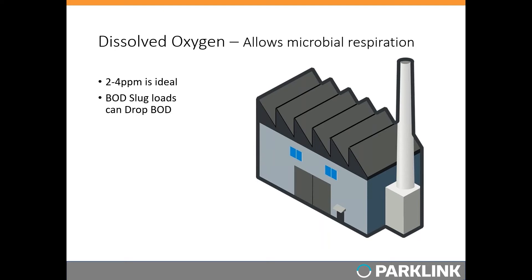Another way dissolved oxygen becomes an issue is a short-term drop related to a slug load of high-strength, soluble, easily utilized BOD. Heterotrophic bacteria use those high-strength slug loads very quickly and have a high oxygen requirement, sucking out a lot of oxygen in a short period of time. If that low DO persists for 24 hours or more, it can definitely knock out a population of nitrifying bacteria. Some plants do well at lower than 2–4 ppm DO — that's just an ideal range for a typical activated sludge plant.